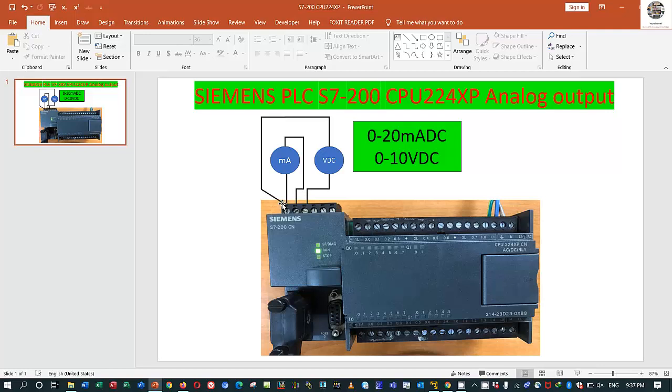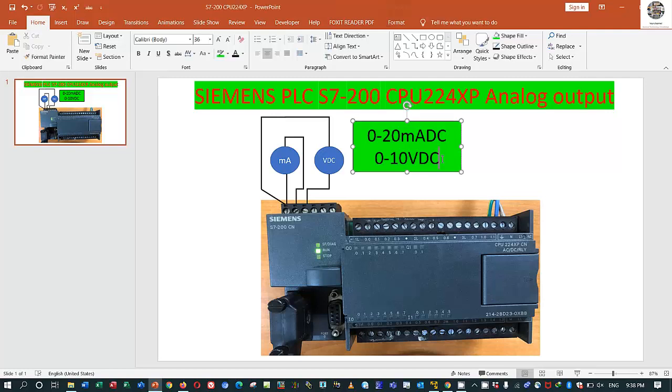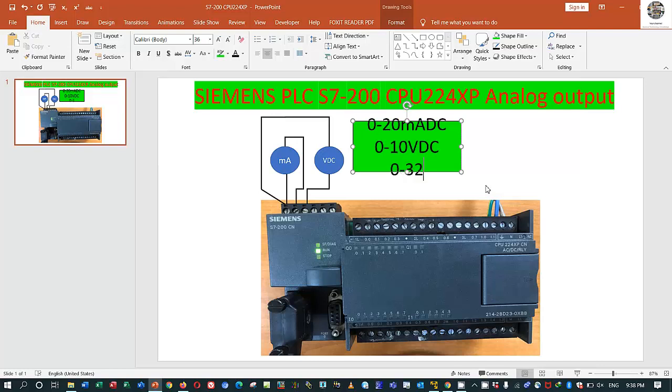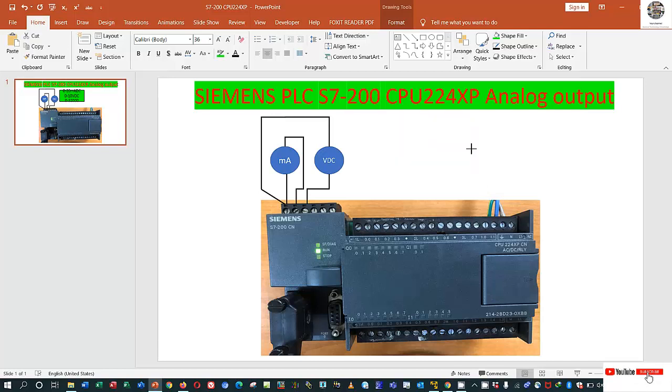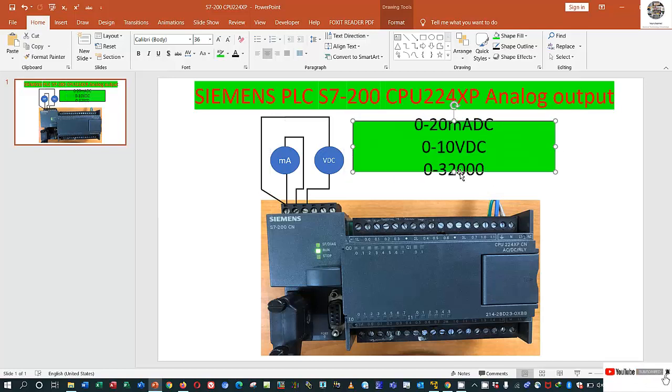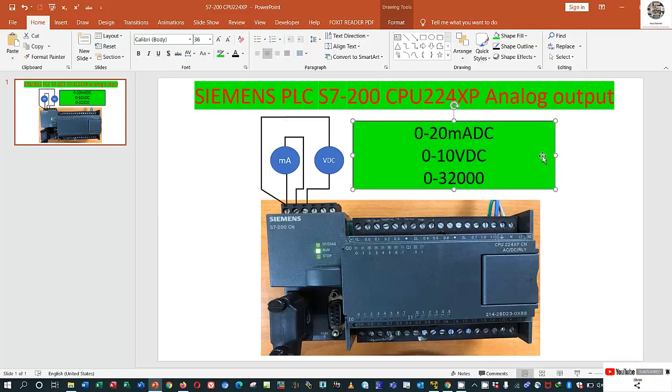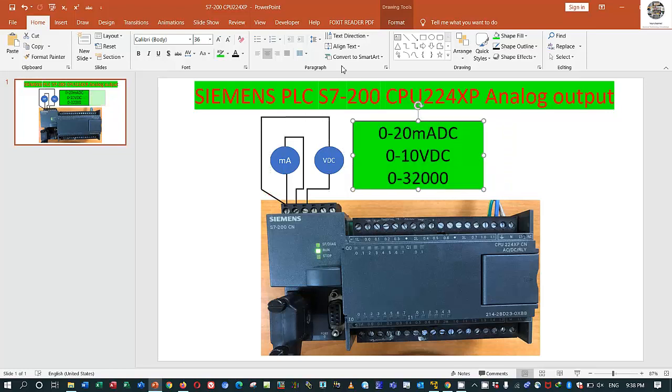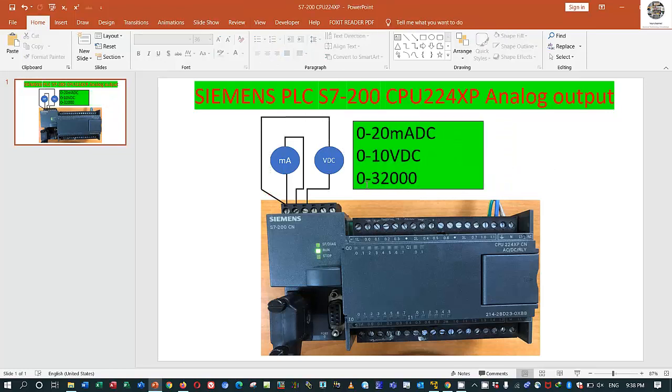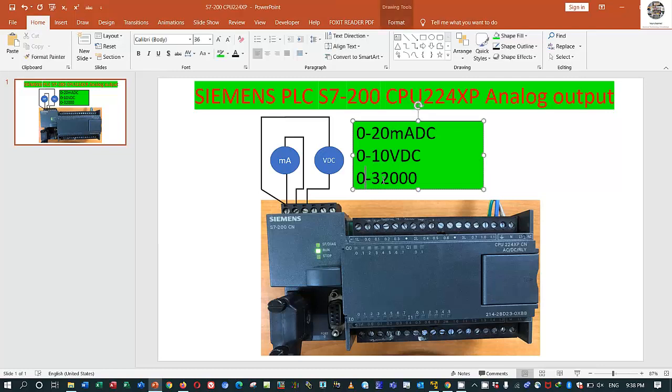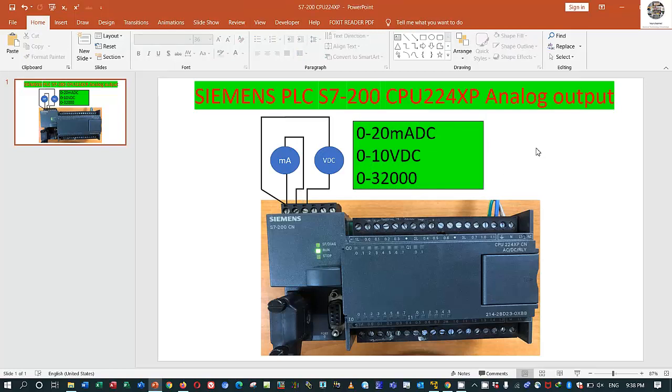If we measure from this terminal to this terminal it will generate milliamp from 0 to 20 milliamp. If we measure from this terminal to this terminal it will generate from 0 to 10 volt DC. The raw data comes from 0 to 32,000. It means that when we source 0 from the software Step 7 it will show 0 milliamp and 0 volt from the other terminal. So let's test together. Let's go to software.